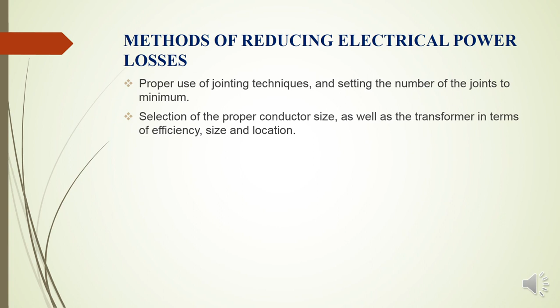They also look at the load assessment of the area which they want to electrify, to determine the required rating of transformer that can withstand this amount of load. The third method is the regular inspection of connections, isolators, dropout fuses, low tension switches, transformers, transformer bushing system, and other distribution equipment. The fourth method is the direct feeding of heavy consumers from the feeders.